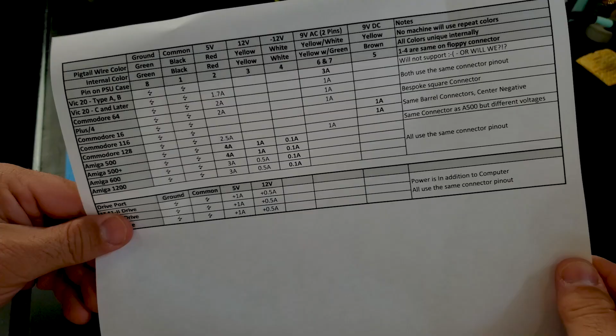Taking a look at the power table, and specifically the colors across the top, you can see we've assigned colors for both the cables and the internal wires. The reason those are different is the pigtails are done with 5-conductor cable. Since there are only 5 colors, some have to be reused, but we've organized them so no machine will use the same color more than once.